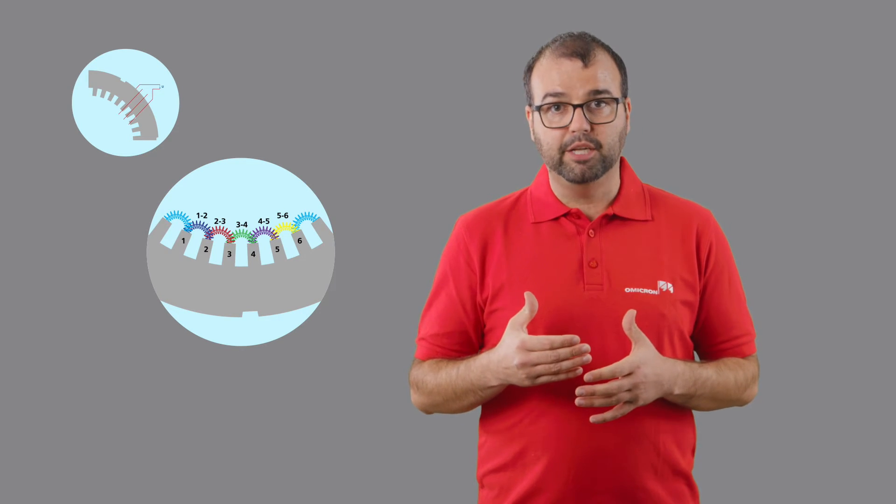The detection of potential issues happens via a sensor, a EL CID or Rogowski coil, which is moved along the surface of the stator core. A higher reading in the measurement indicates a higher eddy current.